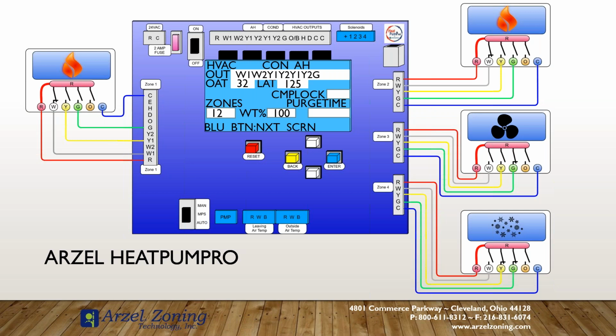We can see that it says zones 1 and zone 2 are being served. So that's in the lower left-hand corner of the screen. It says zones 1, zone 2, or 1, 2. It's not 12, that's zone 1 and zone 2. So we can see that we have those 2 zones being serviced. Their weight adds up to 100%. And one of the things with the Arzel HeatPumpPro is that your weight percentage does not have to total out to 100%. It can be less than 100. It can be greater than 100. If you want to know how the zone weighting works, let us know. We do have a training for the zone weighting specifically to go over the Heat Pump Pro settings and give you more in-depth information with that.